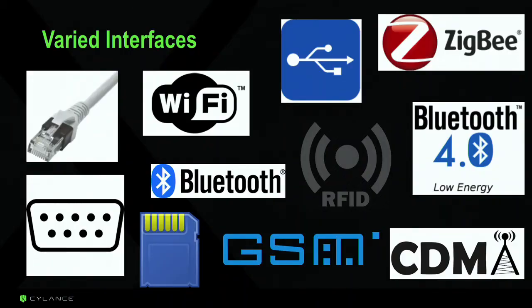Medical devices communicate in many different ways — a big change from years ago when infusion pumps would just have RS-232 serial interfaces with not much external attack surface. Over the last number of years that's branched out significantly, mostly due to demand for functionality. As functionality increases, so does attack surface.